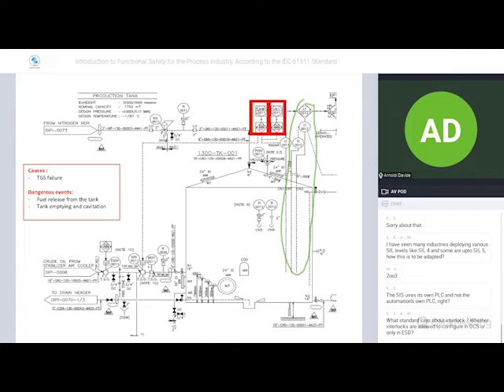At this point, after the HAZOP, we established that the risk of this hazardous scenario was very high. And during the SIL allocation, we established the requirement of two different SIFs. The first one was for high level, in order to protect against release of the crude oil, by closing the inlet crude oil valve of the tank. The second one was to protect against low level. They were two different functions from the same transmitter.